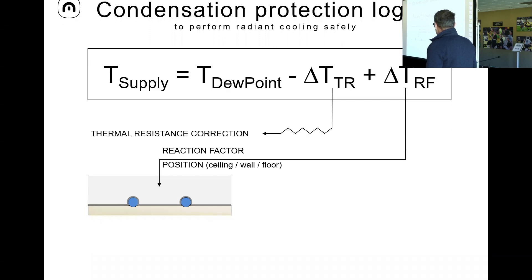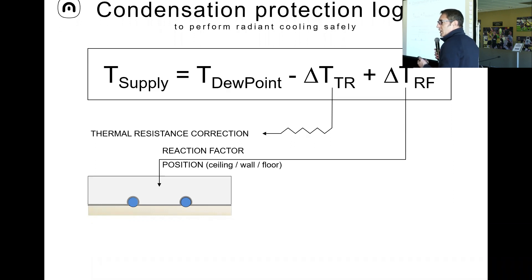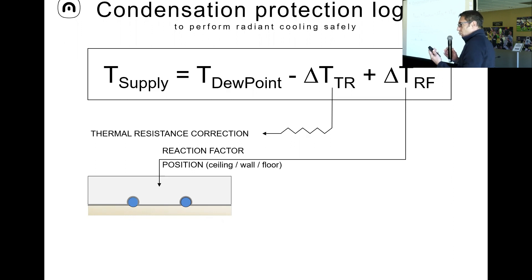If we want to be very close to the dew point at 18°C, the delta T through the gypsum is about 5 degrees, so 18 minus 5 equals 13 degrees — we could potentially push 13 degrees into the system and get 17 degrees on the surface, very close to the dew point. But we don't want to do that. We need to keep a safety distance, and this reaction factor is that safety distance.